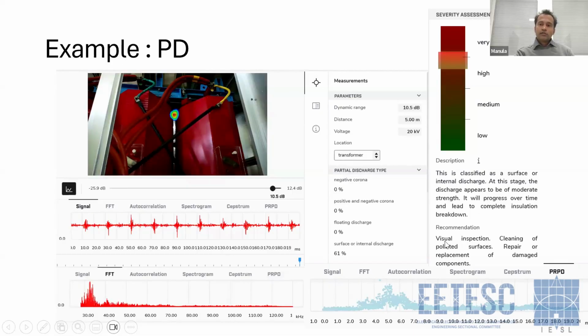And it gives recommendations like doing a visual inspection, cleaning a polluted surface, repair or replacement of a damaged component, this kind of general recommendation. And it gives the relative severity. In this case, it is very high severity. Some users want to look at the time signal and the Fourier transform or the spectrum, what kind of frequencies it has, and the PRPD pattern. All of these post-processing things can be done with these tools whenever the user wants.